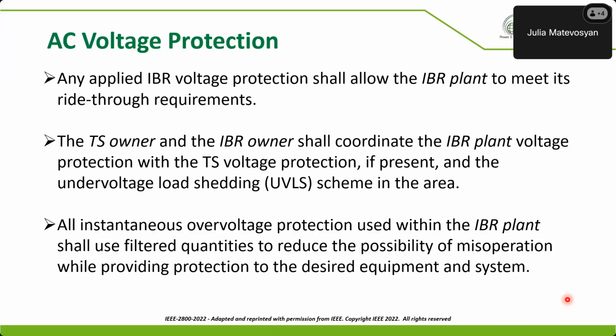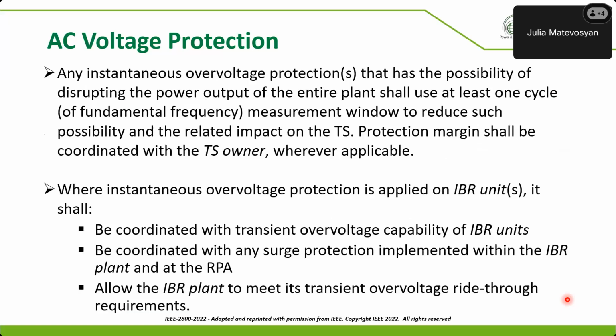Now, the reason for this was that unfiltered quantities might have some transients that might trigger instantaneous protection. If you use filtered quantities, then some of those transients are filtered out, and the protection becomes more reliable. So to reduce the possibility of misoperation, the standard says to use filtered quantities in any instantaneous protection. A few more details.